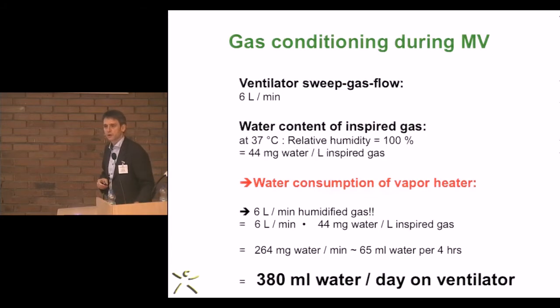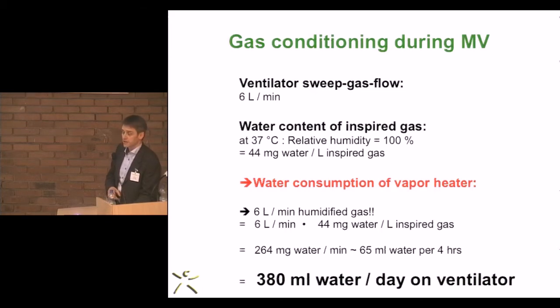Some ventilators you can set the flow and then you can recalculate. Others are in the demand flow mode and you don't really know how much gas they are using, but it's around that number or even a little bit higher, like 8 or 10 liters, and then you have to recalculate. But you know, if you have 100% relative humidity at 37 degrees, you want to use up to 44 milligrams of water per liter inspired gas. Now, a lot of this water actually gets lost in the expiratory limb, of course, but the amount of water your heating humidifying chamber is using, you can calculate that with these given numbers, that should sum up to about 380 milliliters of water per day on the ventilator.